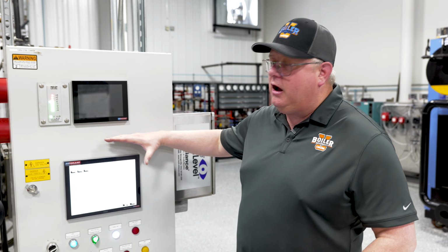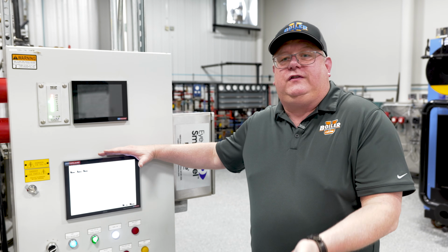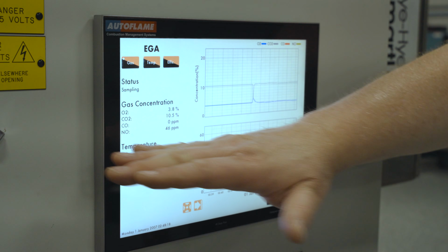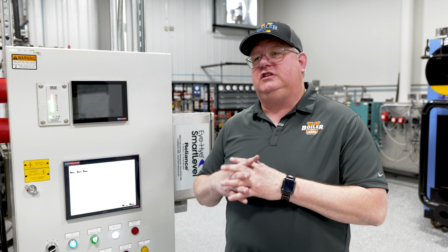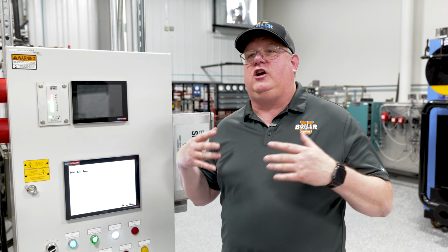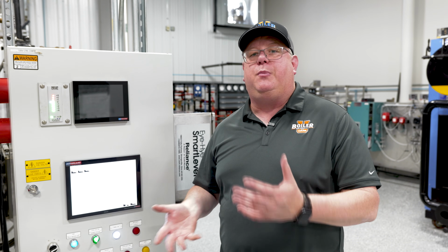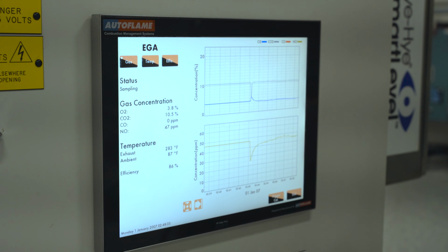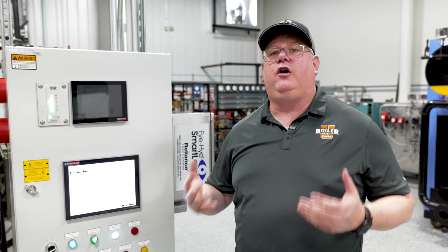So depending on the burner that we've got, our lowest O2 reading is going to correlate with a point where we start to make CO. Because we don't just have extra, we need extra in the right place at the right time. So depending on the burner design, at low fire, we may be able to run O2 at 3%, or we may need to run it at 11%. That's totally a function of the burner design.